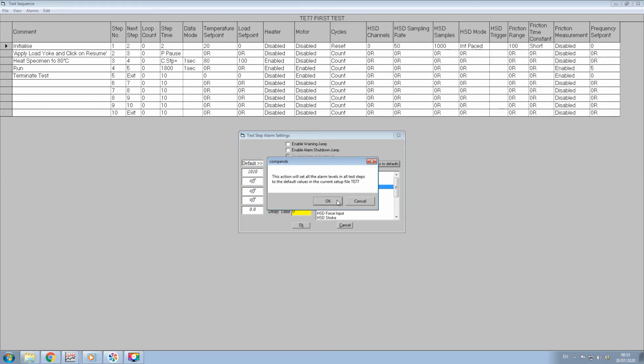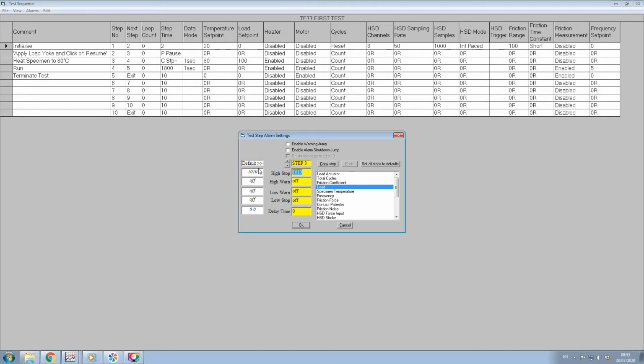Use the up and down arrows next to the step number box to pick each step. Then set the alarm levels for the required channel from the list on the right. The alarm levels may be copied from one step to another using the copy step and paste buttons. When an alarm is triggered, a message will appear above the control panel and the event will be recorded in the data file. A shutdown alarm will terminate the test.